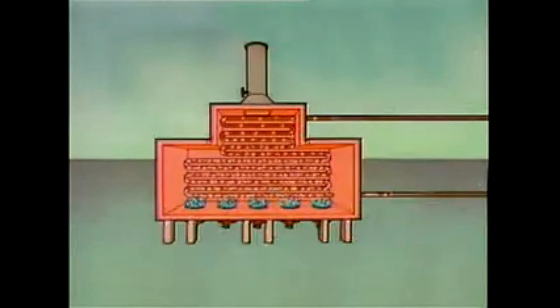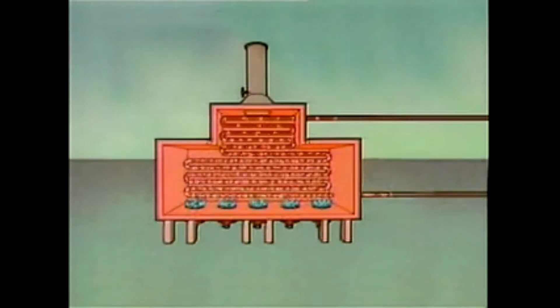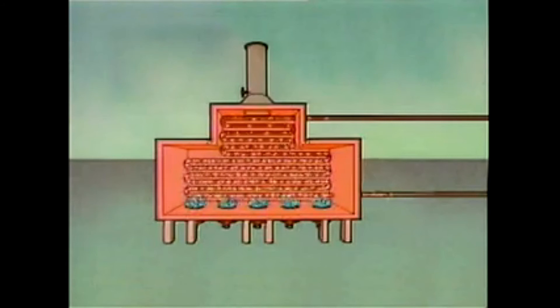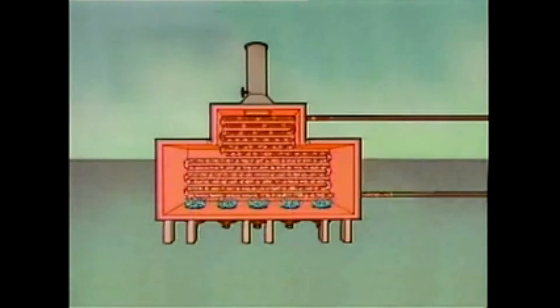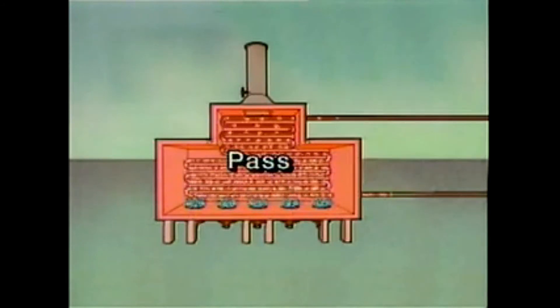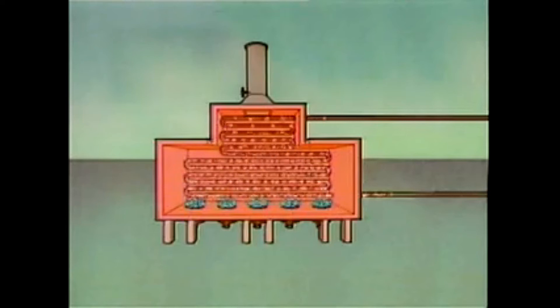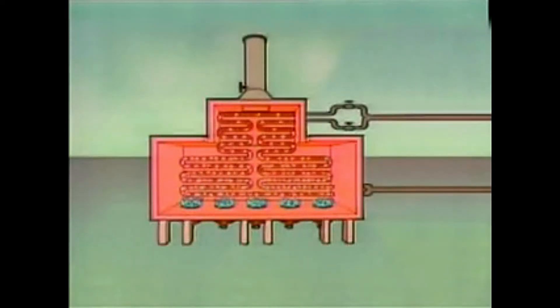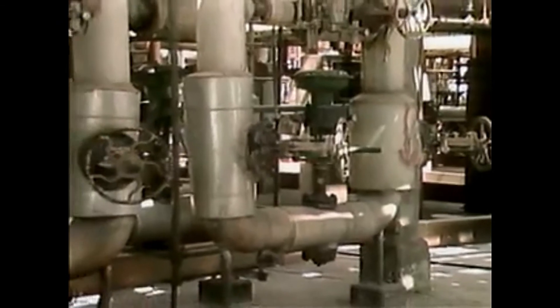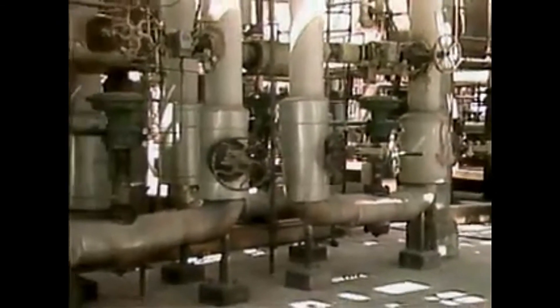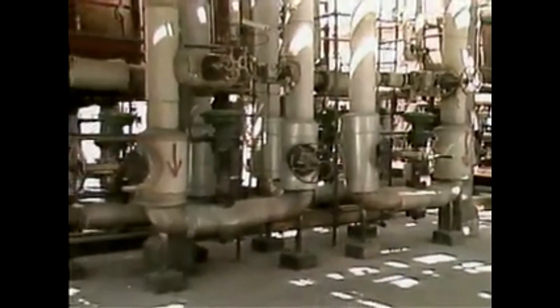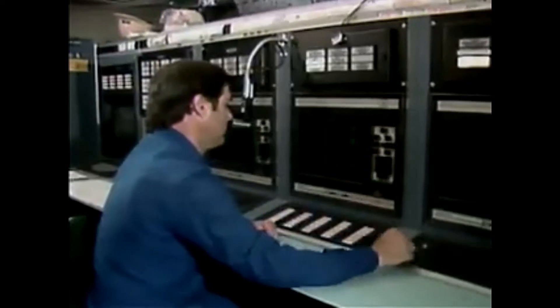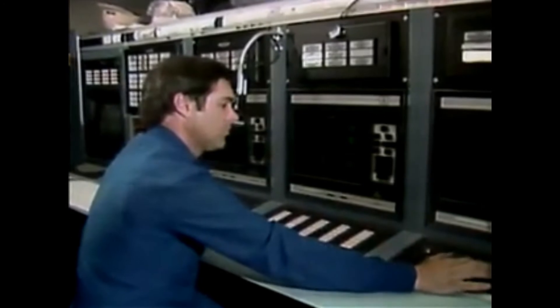The route that the process fluid takes as it flows through a furnace depends on the design of the furnace. Each continuous uninterrupted path that the fluid takes is called a pass. This furnace is a single pass furnace, but many furnaces are multi-pass types. The flow rate of process fluid through a furnace is regulated by valves — usually a control valve for each pass — and these valves are often operated automatically as part of a control system.